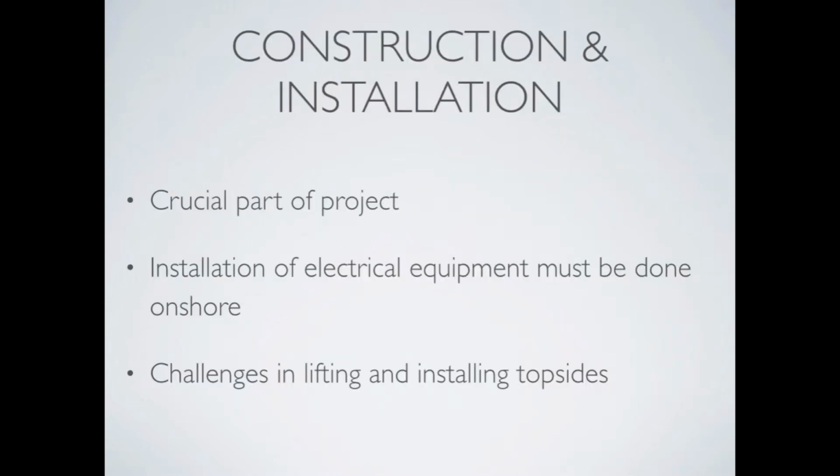The construction and installation phase is a crucial part of the project. The electrical equipment is very sensitive to movement and will need to be secure during transport. There should be no installation of electrical equipment offshore. The crane vessel required to lift the topsides offshore is one of the largest in the world and its availability is limited. Therefore, it is best to eliminate or reduce dependency on such vessels.